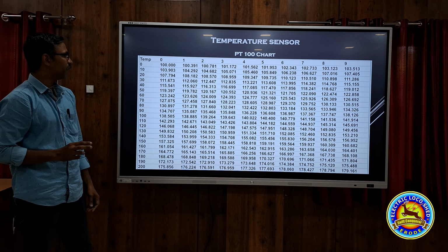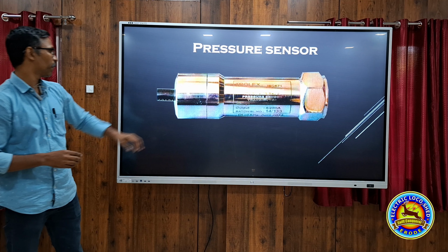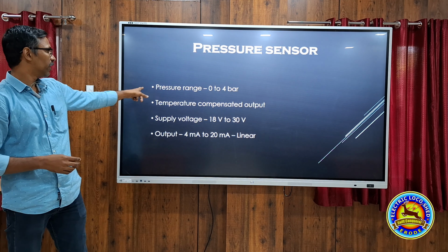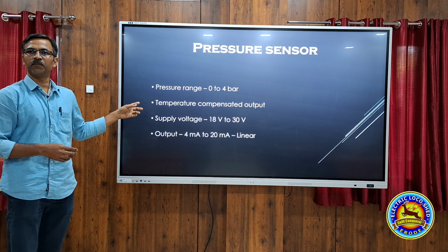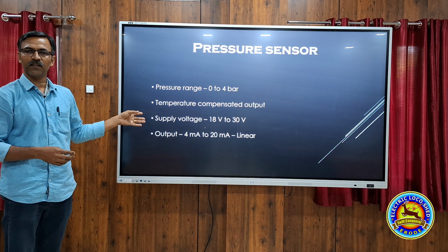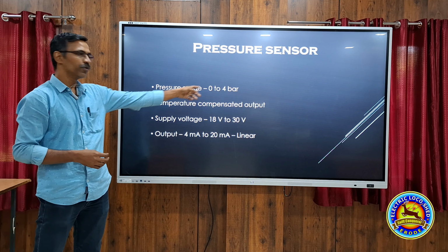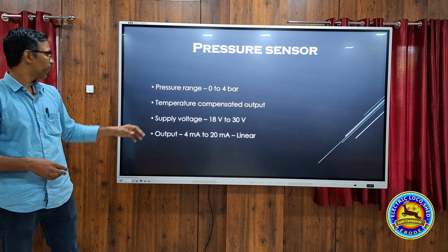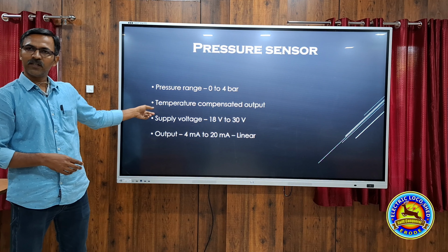Next is the pressure sensor. The pressure sensor is a piezoelectric item. When pressure is applied to the piezoelectric crystal, the resistance of the crystal will vary, and accordingly the current flowing through the sensor will change. The pressure range of the pressure sensor that we are using is 0 bar to 4 bar. That is the output.